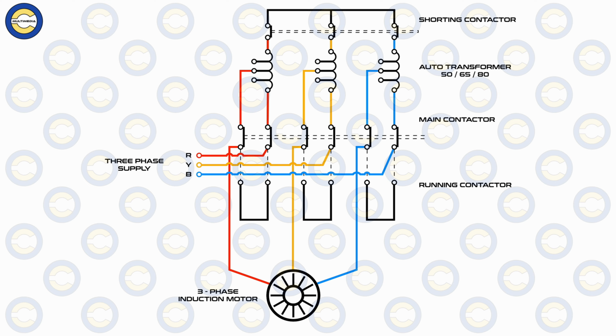Why this type of design is not very common on board ships is because we normally have designs where the output load is not very high, in parallel to the industrial loads that are required on land. And also the transitions during the starting can commonly be handled by contactors and timers and not the tap changers. So there is a very big gray area of design compatibility and also the application for the maximum range of load that we are intending to use it for. And thus the usage is not very common, but it is there definitely.